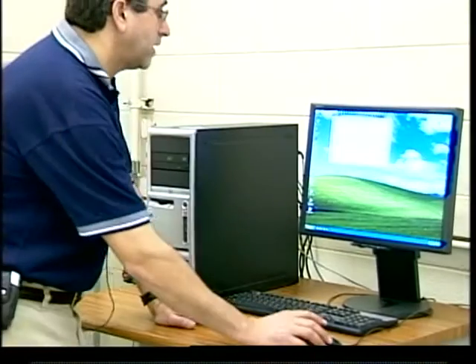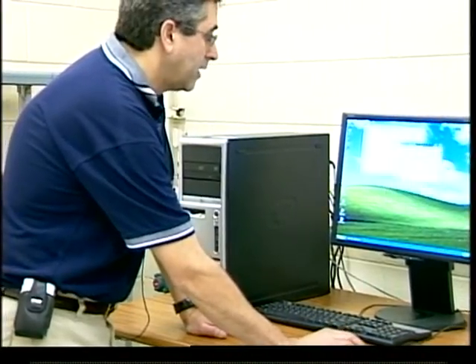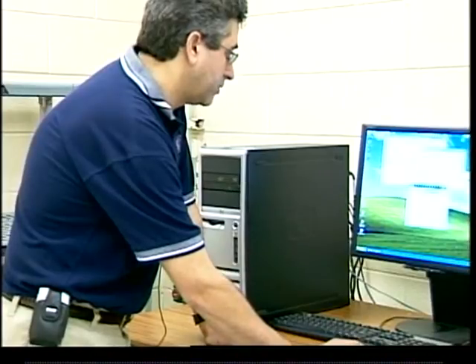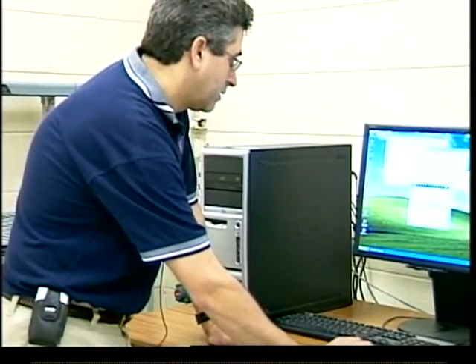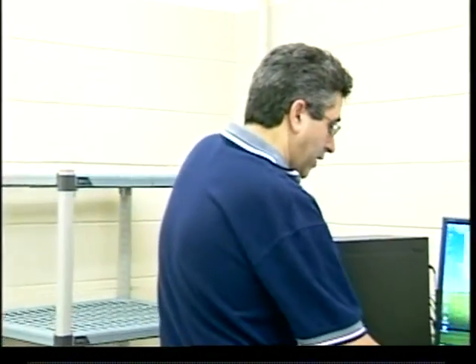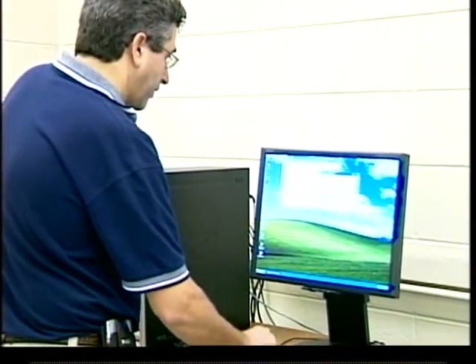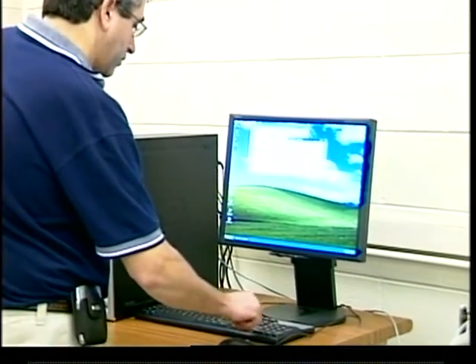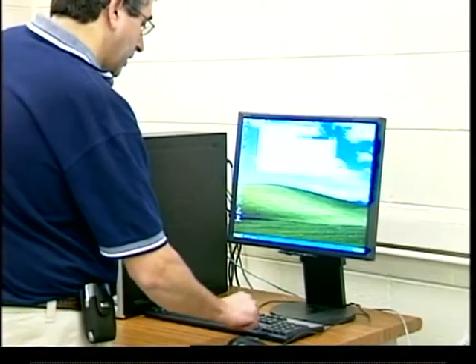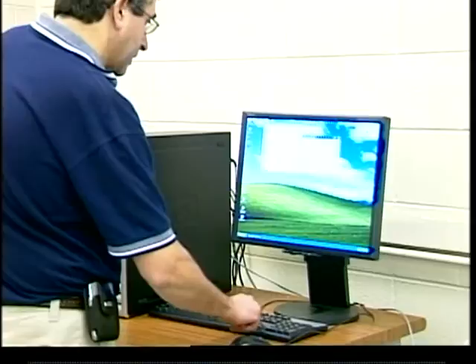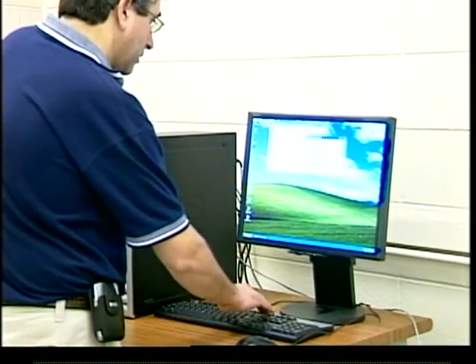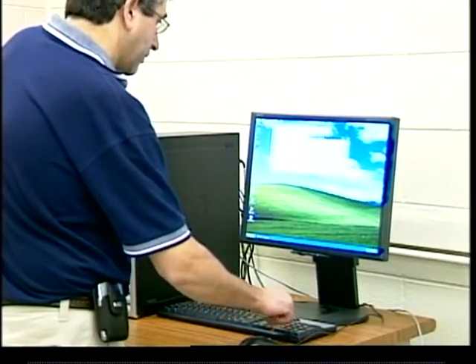So I am going to jump directly to what's called calibrate machine. Now, I'm going to put the stresses in TSF. What I need to do is put the stresses that I am actually going to apply when I run my actual consolidation test. Where those stresses come from, the ASTM has a recommendation for that. So it starts with 1/8 of a TSF, 0.125. Then you double the stress: 0.25, 0.5, 1, 2, 4, 8, 16, 32, and you unload it: 8, 2, 0.5, and 0.125. So I have my stresses.